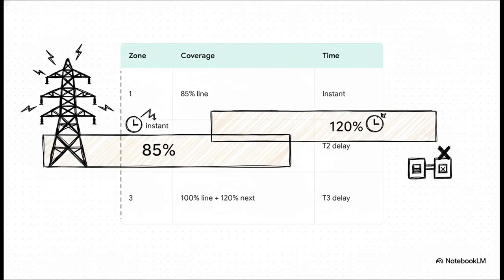Let's break down the hard rules for this stepped system. Zone 1 covers exactly 85% of the transmission line, and it trips instantly. Now you might be asking, why only 85%? Well, because our measurements aren't actual magic. We leave a deliberate 15% blind spot at the far end so we don't accidentally trip the next line's breaker for a fault that isn't even ours.